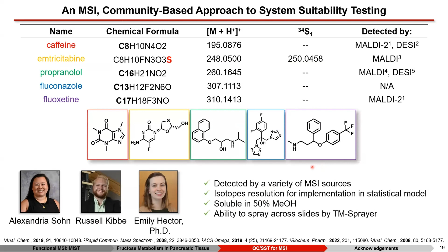We wanted to see if we could make this a really good QC standard. So what we do is we spray a slide with a TM sprayer and store the glass slides at minus 20 degrees until analysis. Then we do the MS analysis, and in this developmental study, proof of concept, we did 118 ROIs when the instrument was clean. When we knew the instrument was compromised, we collected 68 ROIs. And then after we clean the instrument, so hopefully it's back to the beginning in terms of its initial conditions, we collected 10 ROIs.